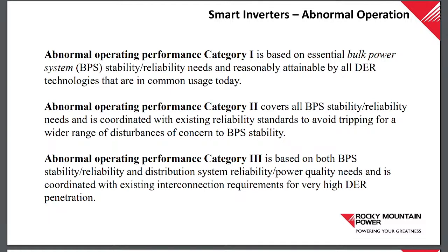That can consequently cause system stability issues. We could lose more generation, we could start to lose load. So this new settings suite allows that type of system issue to be ridden through. That's what this new functionality in the inverters does, giving us options to set it with these three categories.